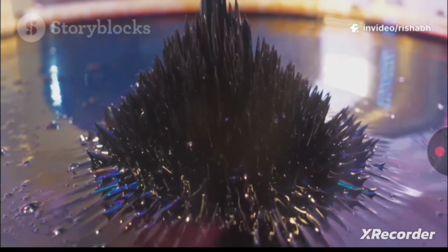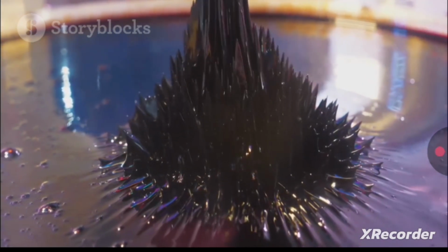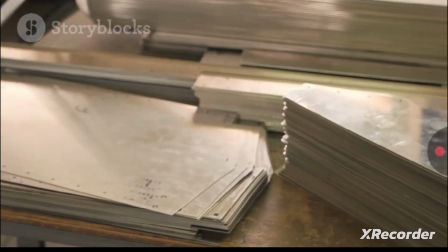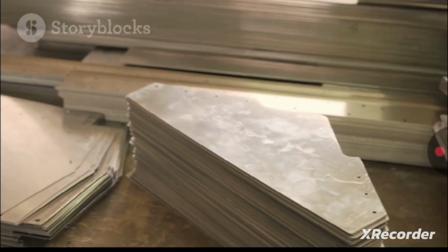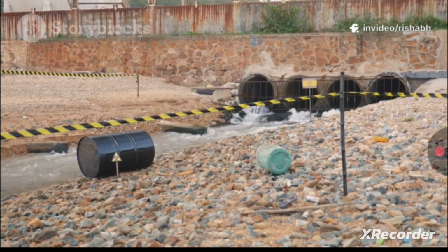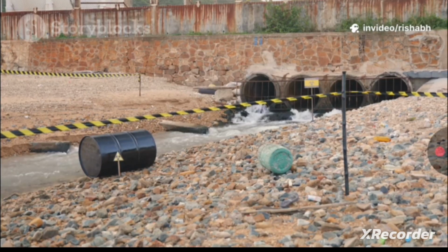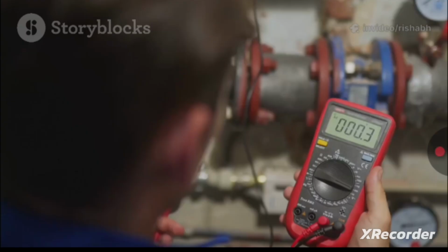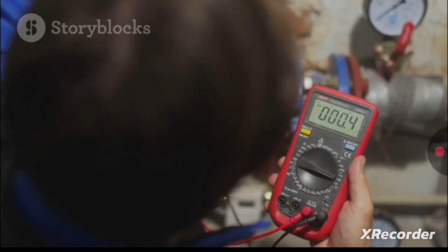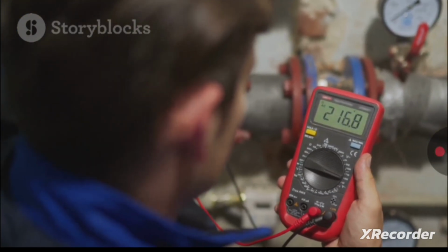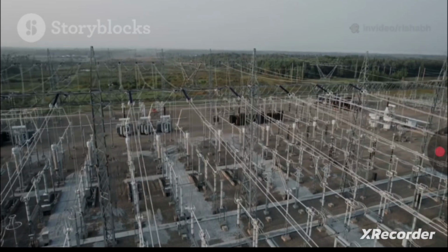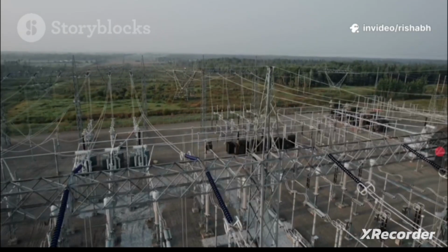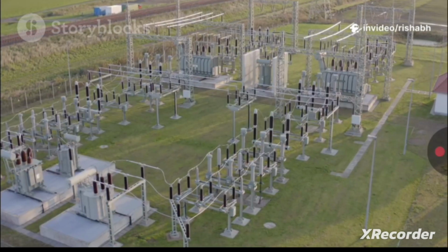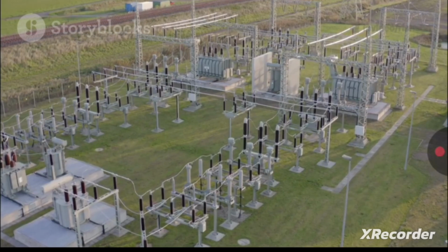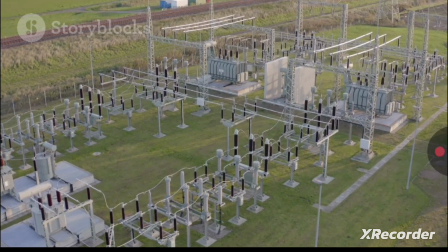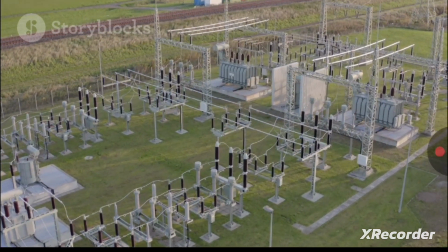Under normal conditions, this magnetic flux is well behaved. It stays neatly confined within the laminated steel sheets that make up the transformer's core. The core is designed to handle a specific amount of flux, just like a pipe is designed to handle a certain amount of water flow. The flux density, how concentrated the magnetic field is, is kept at an optimal level. This ensures the transformer operates efficiently, transferring power with minimal losses. The whole system is in a state of happy equilibrium, humming along quietly as it performs its critical function of managing electrical energy for all of us.